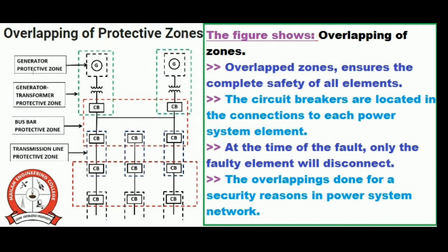Today I am going to explain about the protection zones in the power system. A protection zone is defined as the part of the power system which is protected by a certain protective scheme. It is established around each power system equipment. When a fault occurs on any of the protection zones, only the circuit breakers within that zone will be opened, so only the fault element will be isolated without disturbing the rest of the system.